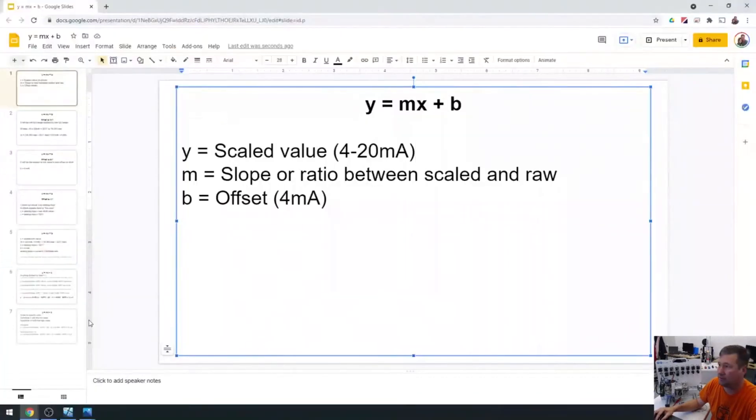And then we're going to have an offset. And the offset's really important on 4 to 20 because it's by far the most confusing thing when it comes to scaling things. We have what's called a live zero. And what that means is zero is not our zero. Four is our zero. So we have to account for that.